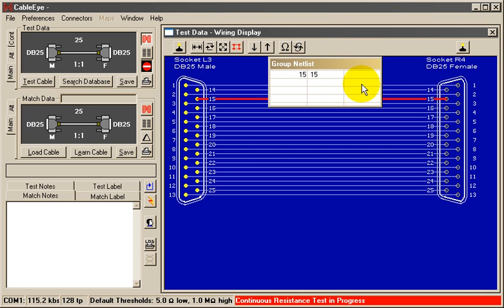As I flex the wire, we see the resistance begin to change, and then drop back to a good connection. This clearly indicates an intermittent problem in this conductor.